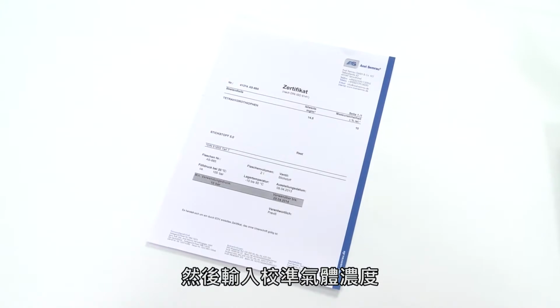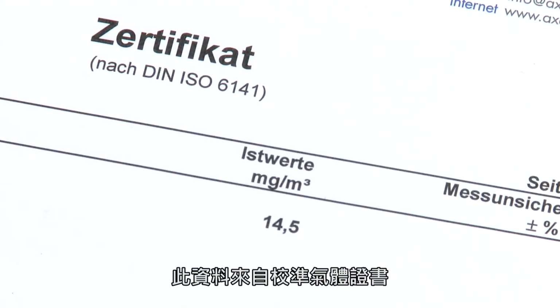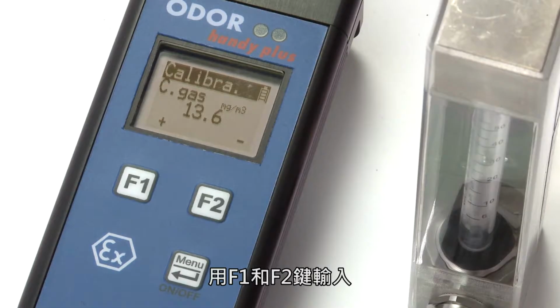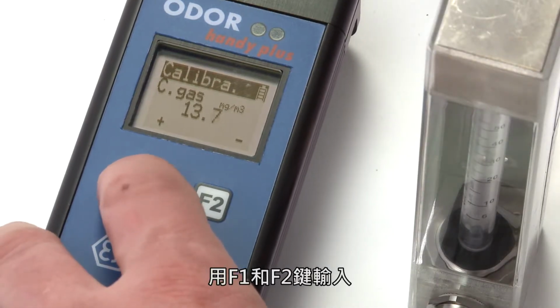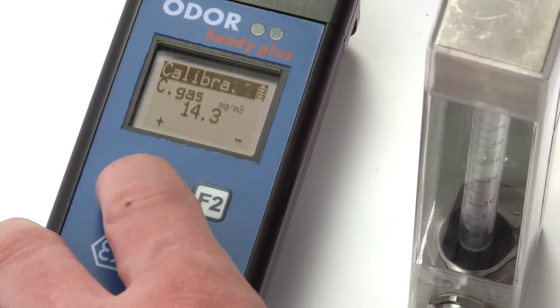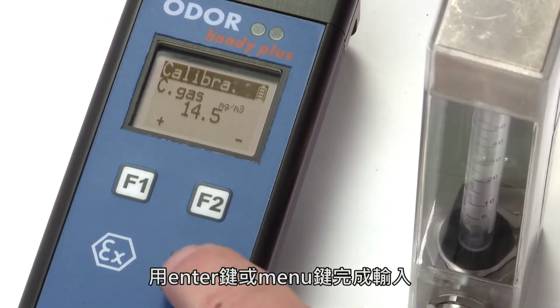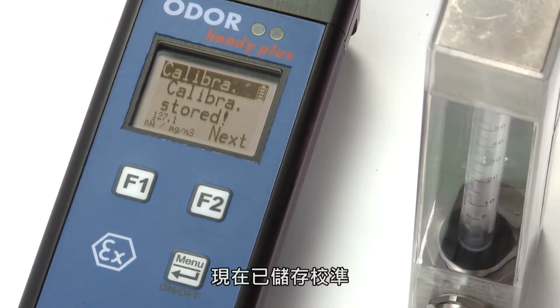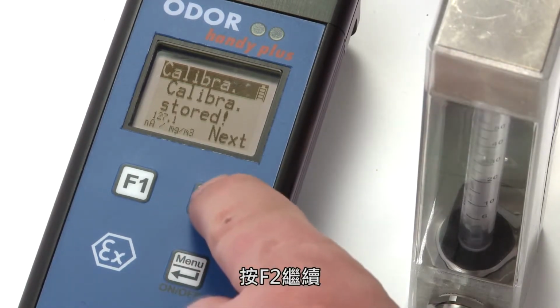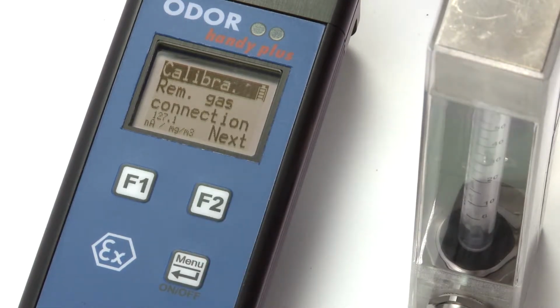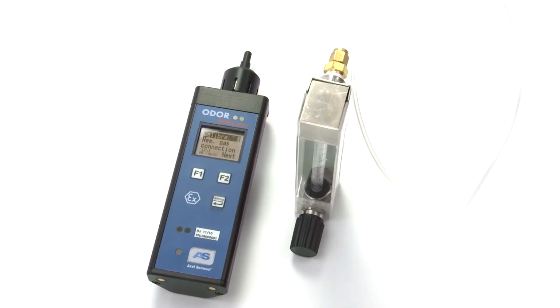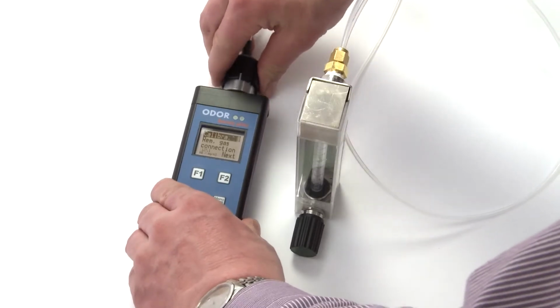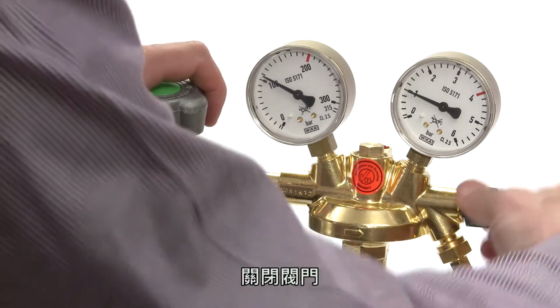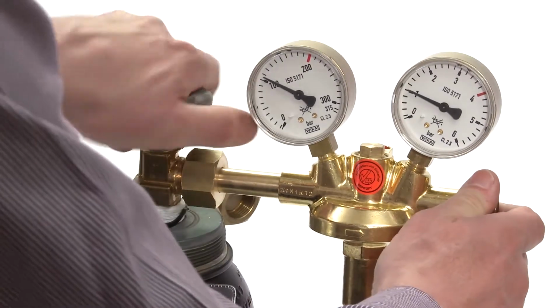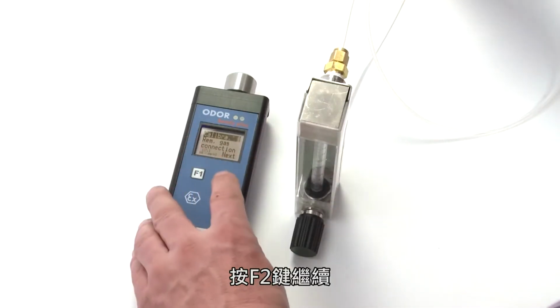Then enter the calibration gas concentration that you got from your calibration gas certificate. Use the F1 and F2 keys for your entry. Complete your input with the Enter key or the menu button. The calibration has now been saved. Press F2 to continue. Remove the calibration gas and close the valve. Press F2 to continue.